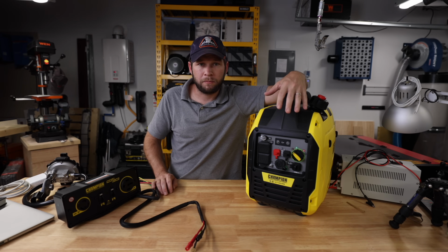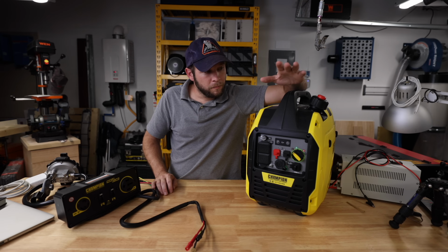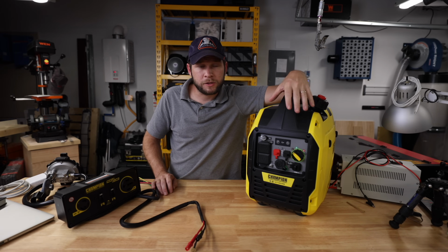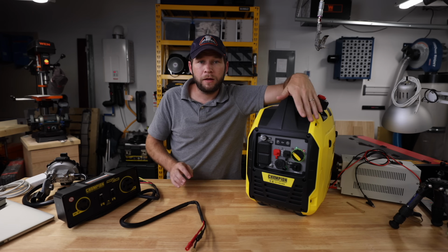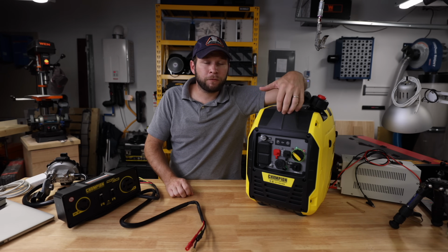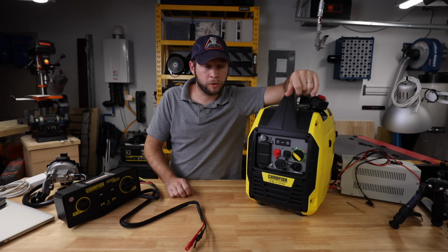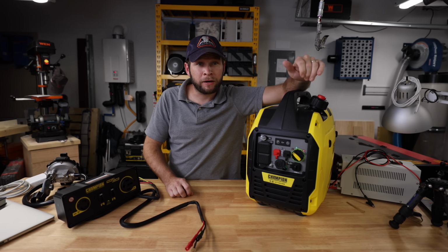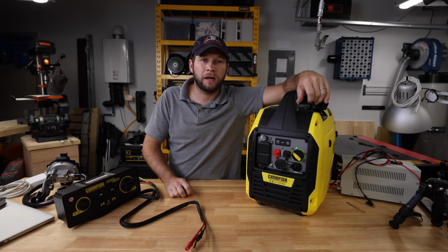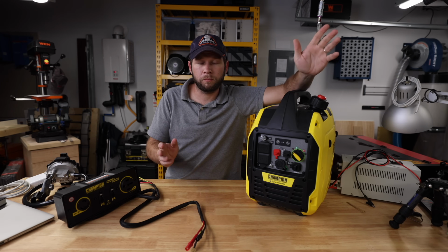So for the most part, the power size you're going to get out of these is not going to be the same as a larger generator, but the power quality is going to be significantly better. These can easily run computers and things. The average total harmonic distortion on a lot of these inverter generators is actually around 1%. So that is better than the power company's electrical power coming through your meter to your normal wall outlet.